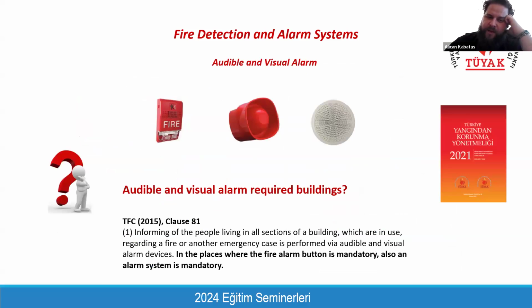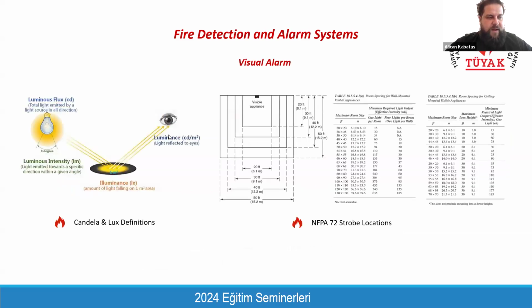And we have some audible and visual alarm system. We need to provide this system, and especially not speakers, but especially strobes are not preferred by architects, but we need to have them according to the Turkish Fire Code and also according to the international standard. For these visual alarms, we are checking the light intensity, so that even if you cannot hear the voice alarm, because you are disabled, or you wear headphones, or you wear some noise canceling type earphones, you can see the visual alarm.